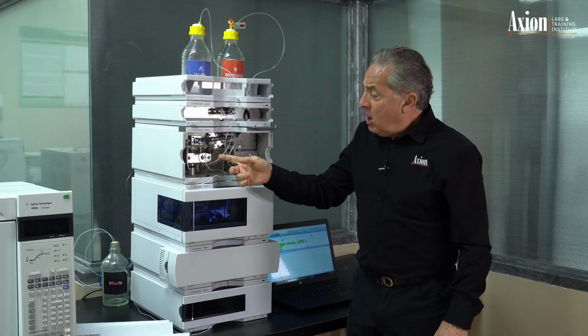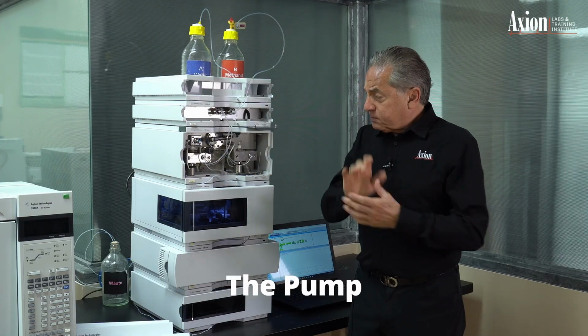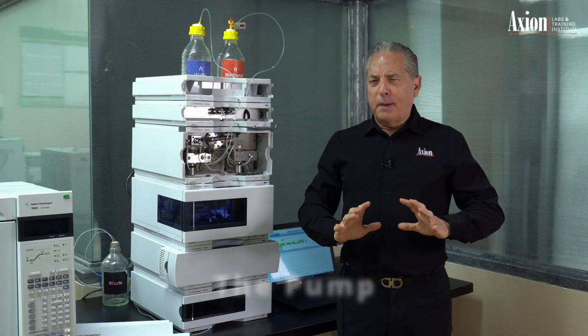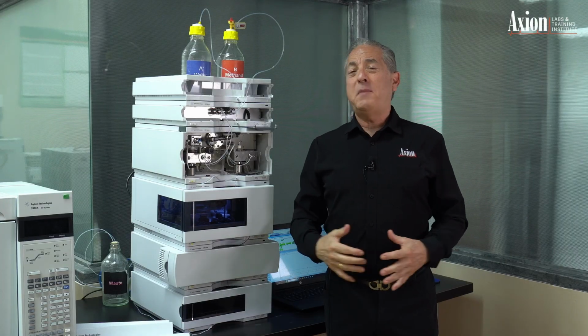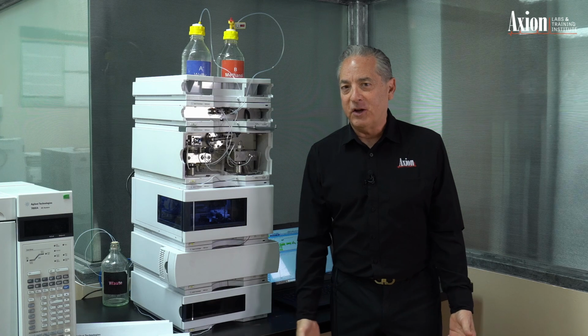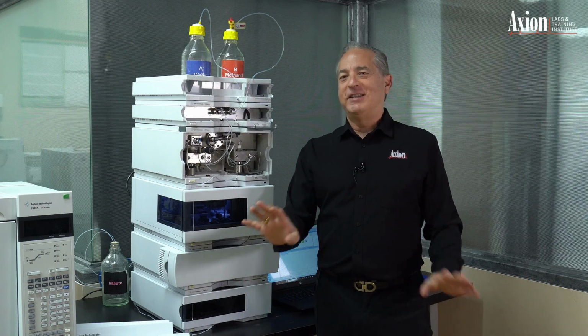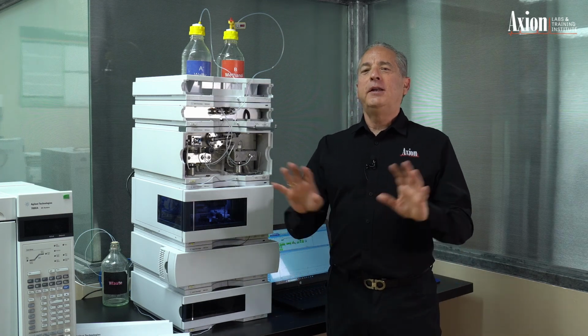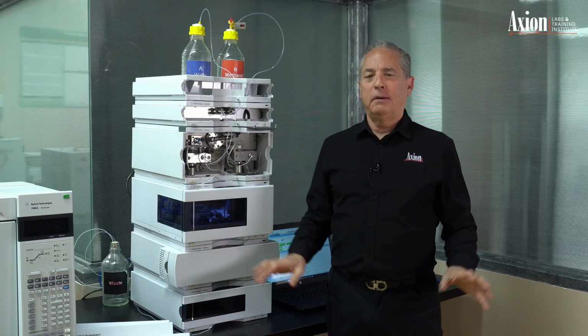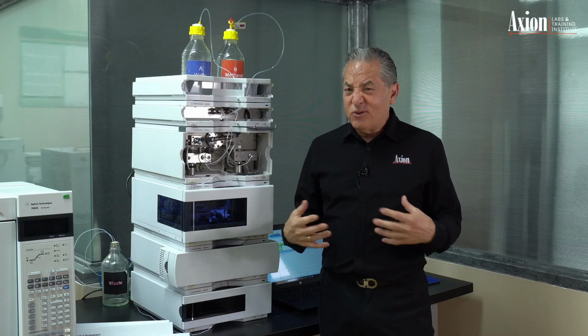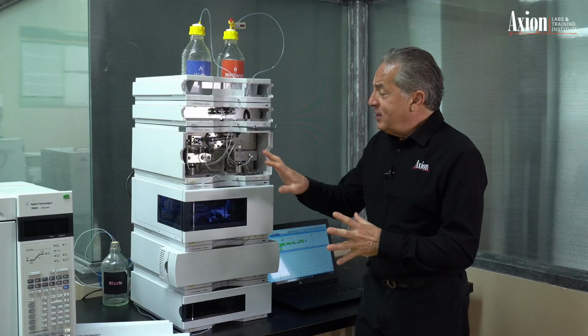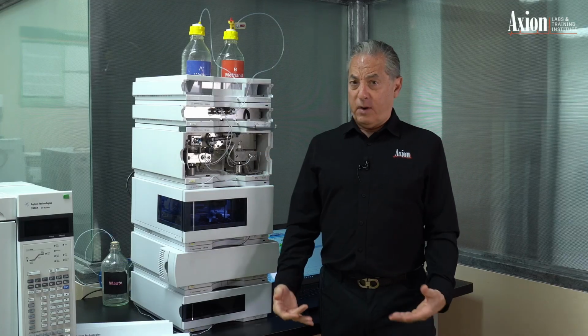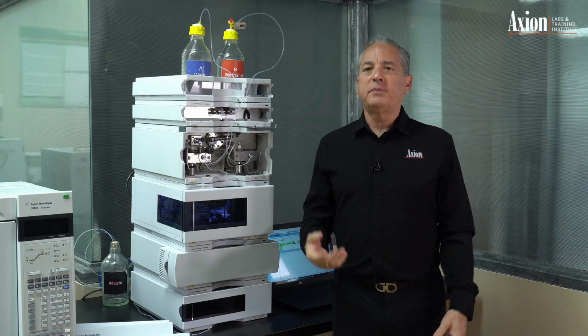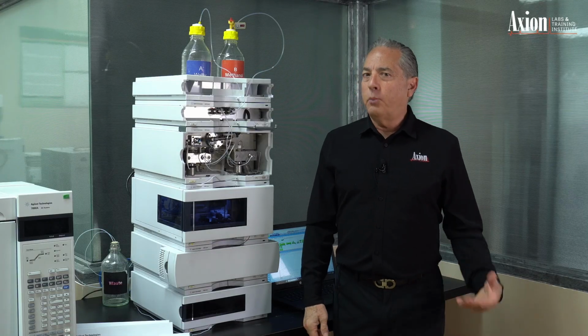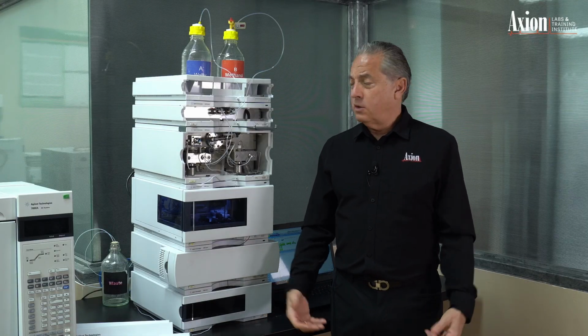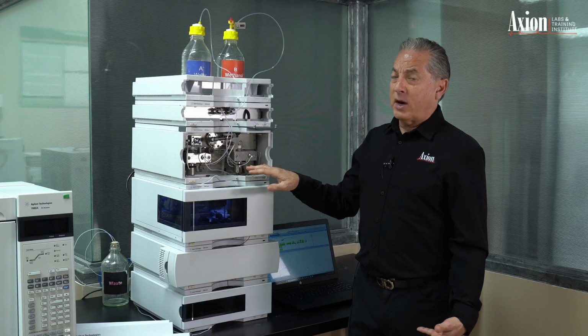So now in this pump design, like I said, there's a couple of pretty common pump designs out there, and all the manufacturers share a lot of similarities. Of course, that would make all my friends mad at each of the different companies, but for the most part, a Ford and a Chevy and a Mercedes all have the same general design on the engines. So in this case, this is called a binary pump. There's two styles of pumps, binary and quaternary, or low pressure gradient and high pressure gradient, which are their official names. So this is what's called a high pressure gradient.